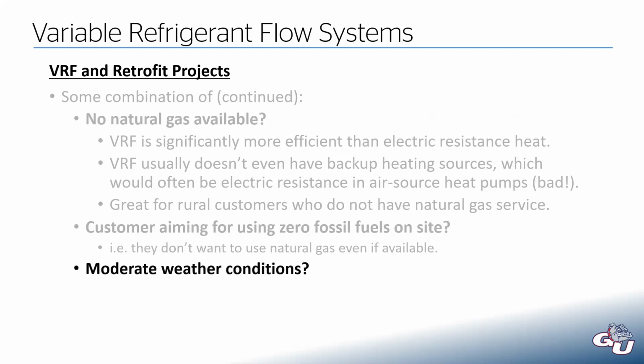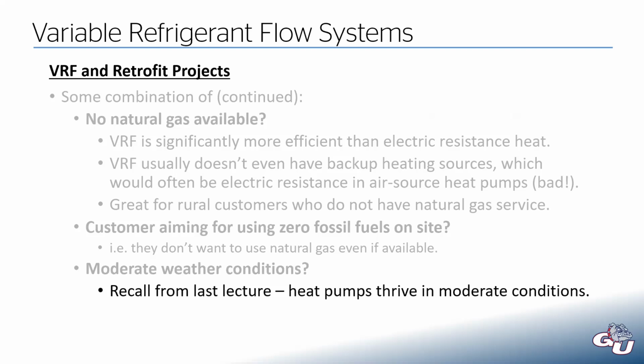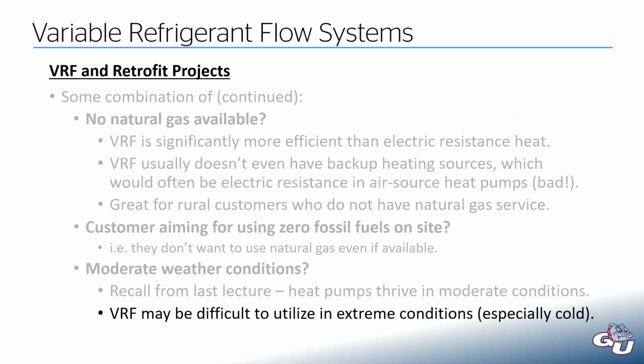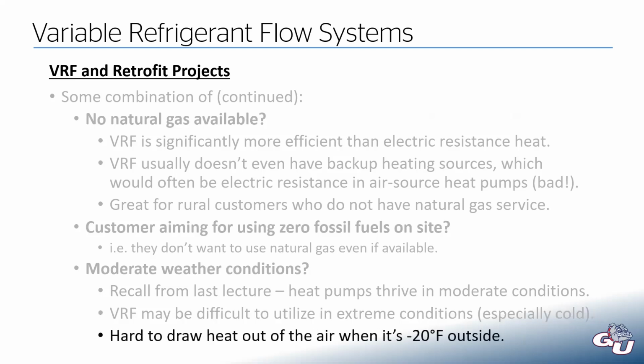If your building is in a moderate climate, so if you have moderate weather conditions, recall from last lecture, this is where heat pumps thrive. This is where they are most efficient. But if you have those extreme conditions, especially on the cold side, although you could have a similar problem if you have an extremely hot climate, where it's 120 plus degrees Fahrenheit, you might have some issues with capacity and having it run well. But it's normally a problem in the cold climates because it's hard to draw heat out of the air when it's minus 20 or even worse. If that's the condition you are in, then you still might need some backup heating sources potentially, or maybe VRF just is not the right move.